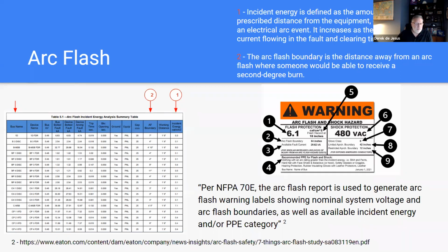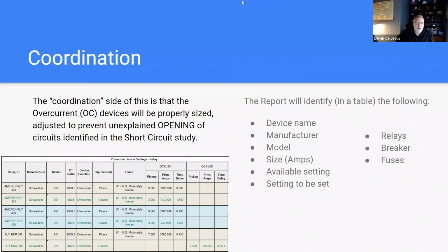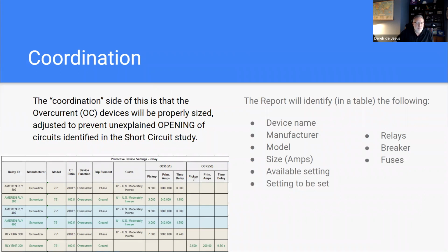And the reason that's important, and I'm going to come back to this table here, let me draw on it, is you're going to be given in this table, and I should have probably picked a different image with breakers, a range or a setting that you need to apply, and that's going to be in this area here. For a breaker, it might say long time function A, and then of that function, it's going to have a time band, and maybe that band is A or 1. And then the short circuit can be based on your initial long time band or a function of the trip unit. A lot of times you might see on your one line diagram an 800 amp frame breaker with a 400 amp trip unit. So you have an 800 AF followed by an 800 AS, 800 amp sensor, or 800 AP, amp plug.